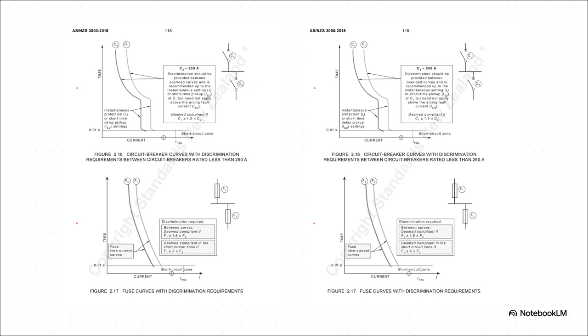But look at the right, for fuses, it's a bit more nuanced. The upstream fuse needs to be 1.6 times bigger for overloads, but a full 2 times bigger to handle a short circuit. It's a perfect example of how the specific gear you choose really impacts the whole design.